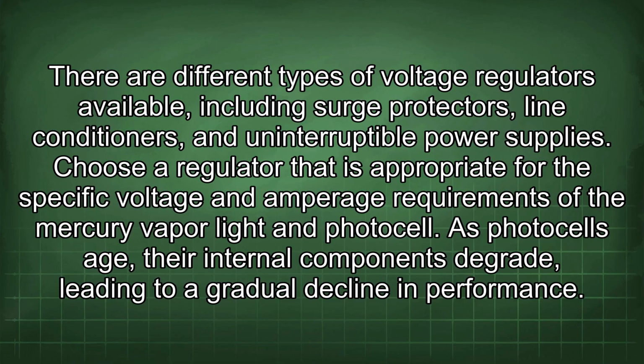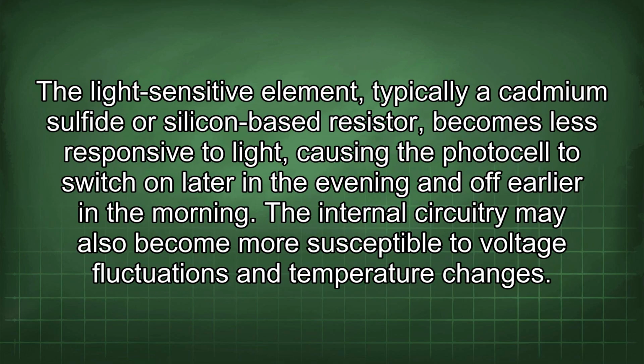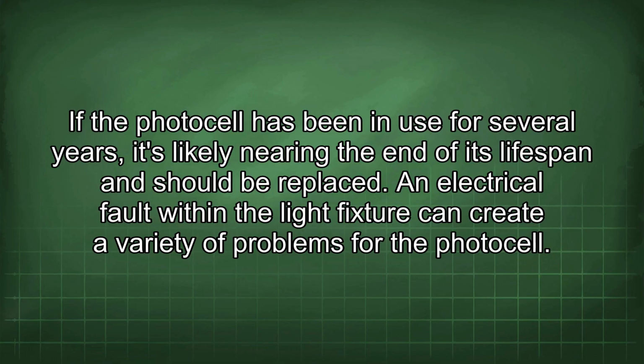As photocells age, their internal components degrade, leading to a gradual decline in performance. The light-sensitive element, typically a cadmium sulfide or silicon-based resistor, becomes less responsive to light, causing the photocell to switch on later in the evening and off earlier in the morning. The internal circuitry may also become more susceptible to voltage fluctuations and temperature changes. If the photocell has been in use for several years, it's likely nearing the end of its lifespan and should be replaced. An electrical fault within the light fixture can create a variety of problems for the photocell.